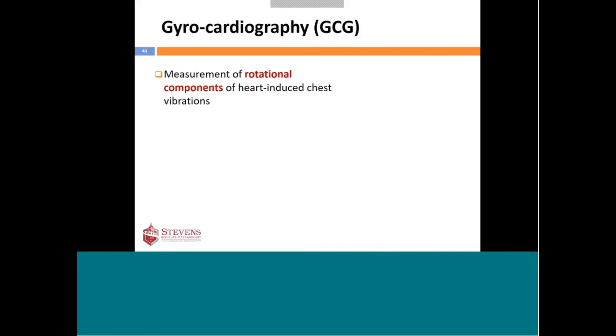Parallel to seismocardiography is gyrocardiography, which is much more recent and measures the rotational component of chest wall movement using a gyroscope. Our group and one other group were the two that recently proposed this method a couple years ago. Combining seismocardiography and gyrocardiography gives more complete cardiomechanical sensing. Seismocardiography provides the z-axis linear acceleration; gyrocardiography provides two rotational axes. Together, they provide direct information about heart valve events and cardiac muscle status. The sensors are MEMS-based — small, low profile, low power, MRI compatible, and easy to apply using just a chest strap without professional electrode attachment.